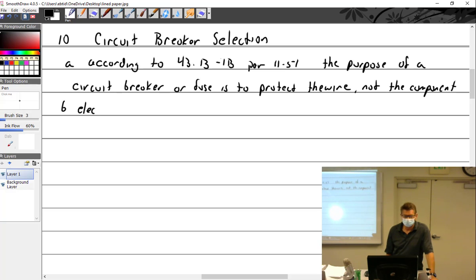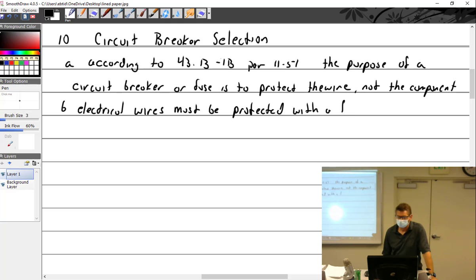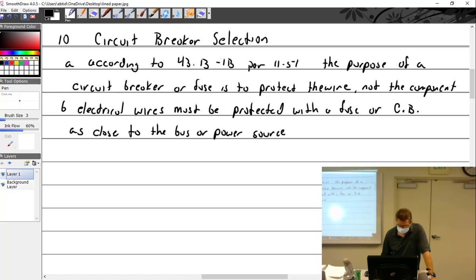Electrical wires must be protected with a fuse or circuit breaker—I'll just abbreviate CB. And what am I going to do with all the time I saved by just writing CB? SeaWorld, SeaWorld, see—as close to the bus bar or power source as possible.